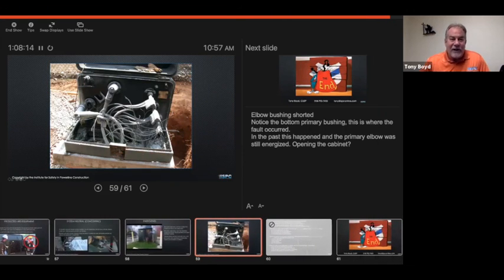You can see on this transformer, the bushing actually blew out of this transformer. So I don't know what it was that caused the fault on here, but in any rate, if this cable is actually being fed from another direction, then it could still be energized. So when I come and I want to know why this transformer is not energized, I would unlock the lock, unbolt the bolt down here, grab this lid and open it up, and possibly this elbow would fall out and make contact, if it's still energized, with this part of the transformer cabinet. I have seen that before.